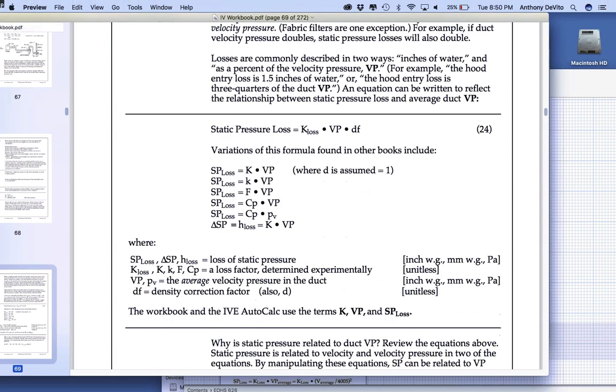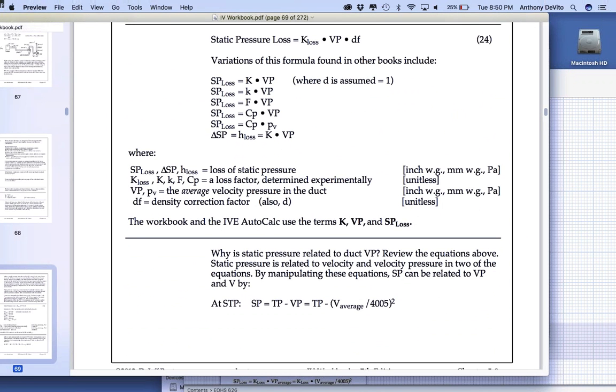Okay, let's go on with this. So now, the way we're going to do this, when we look at the energy loss due to a turn, an elbow, a length of ductwork, a transition from big duct to narrow duct, a merging of two ducts together, we're going to have to make a judgment about what's going to influence how much energy I'm going to lose, how much more energy I have to put into my fan. And like I said before, for a straight duct, it's going to be equal to the length of the duct. It's going to be equal to the roughness of the duct, right? And it's going to be equal to some factor, you know, the velocity of the air going through there. The faster the air is moving, the more energy we're going to lose to friction and vibration and heat and so on and so forth, right?